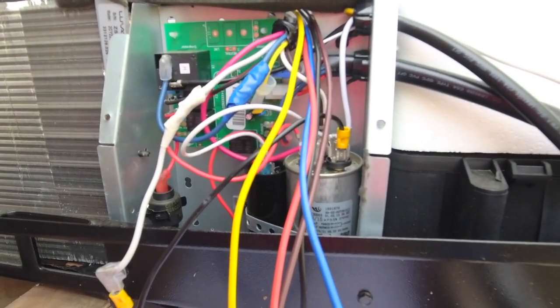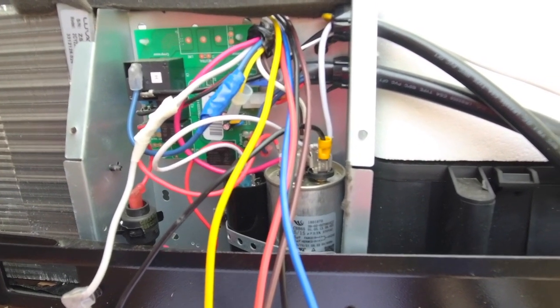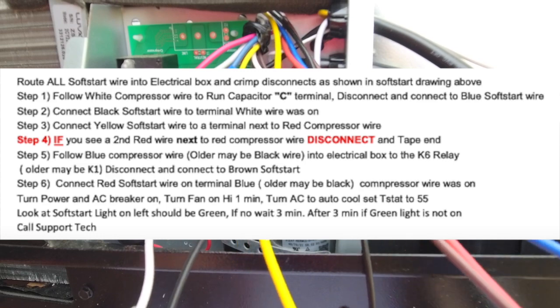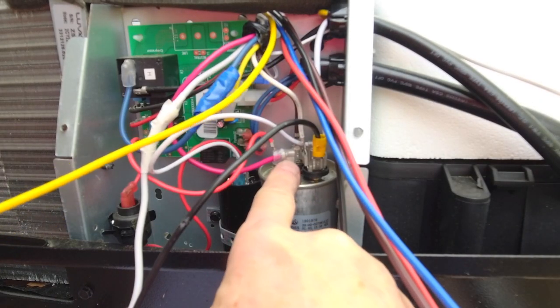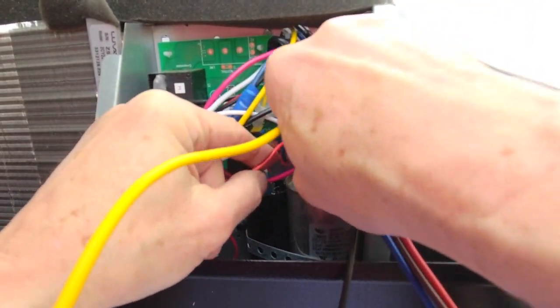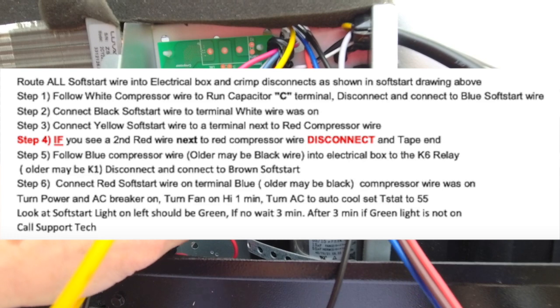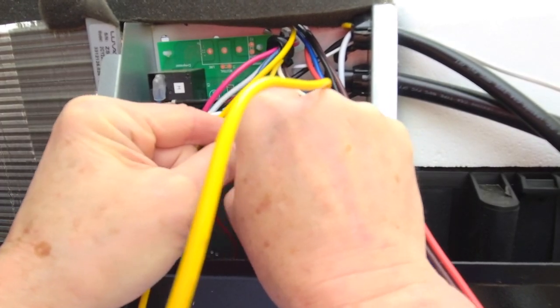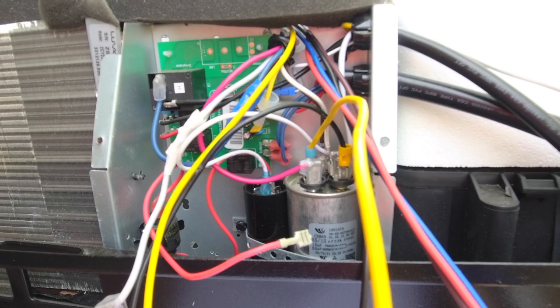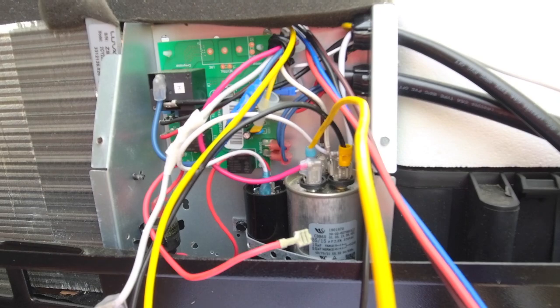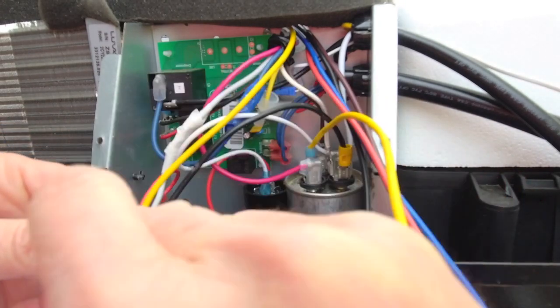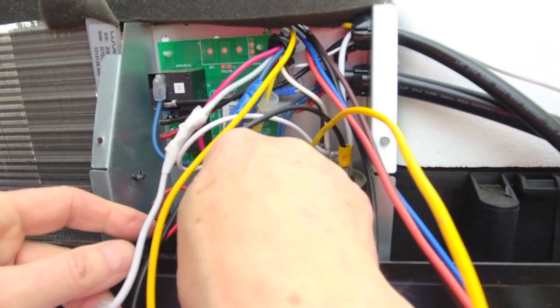Next part: connect the yellow soft start wire to the terminal next to the red compressor wire. Here's the red compressor wire right here and we're going to poke that down here. That's in place. If you see a second red wire next to the red compressor wire, disconnect it and tape the end. I'm going to pop that off and tape that end up to keep him out of trouble. We'll poke him out of the way. All done.